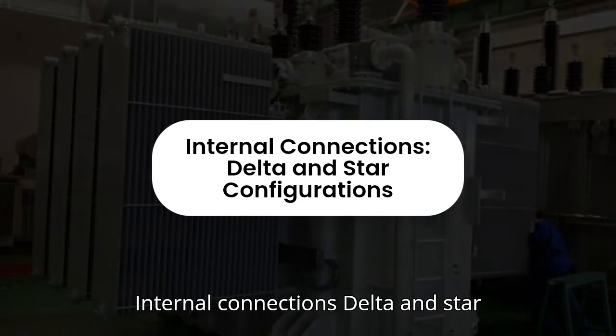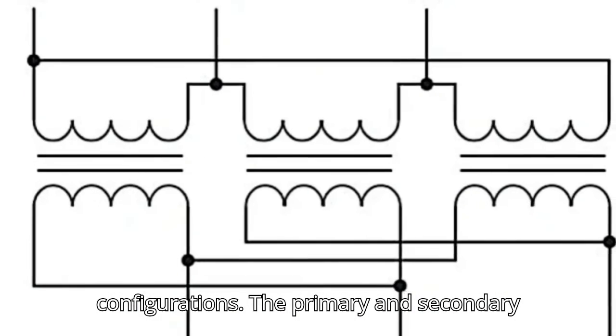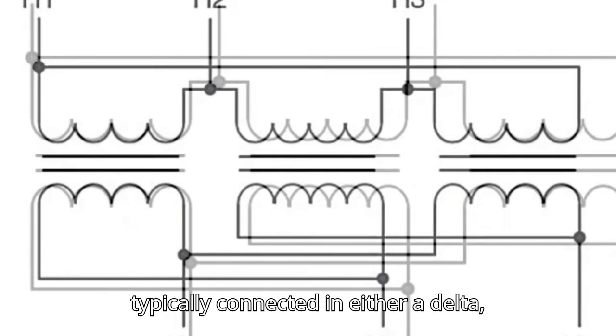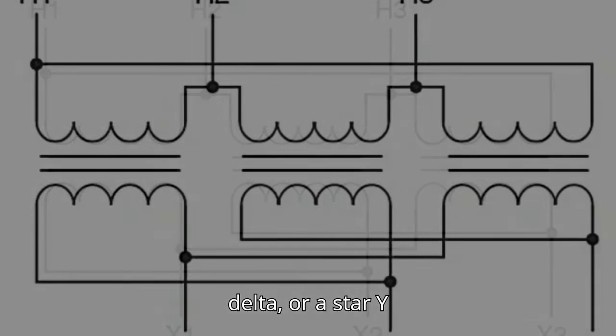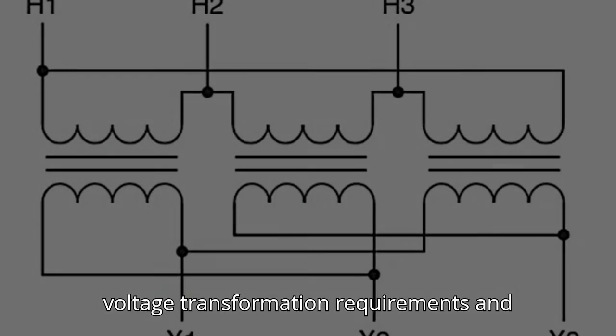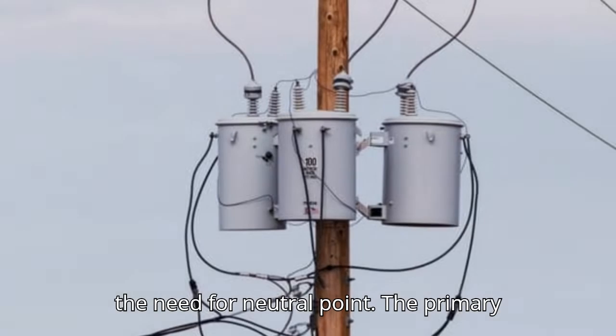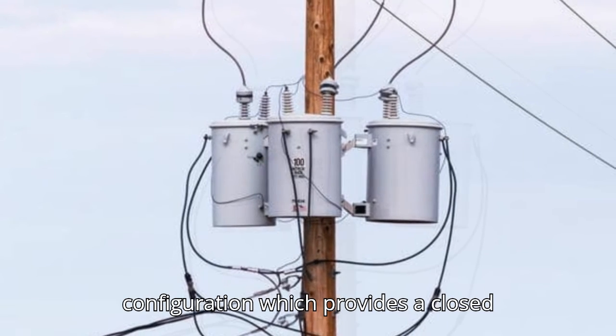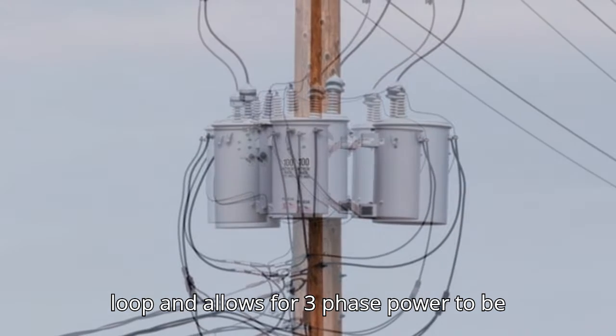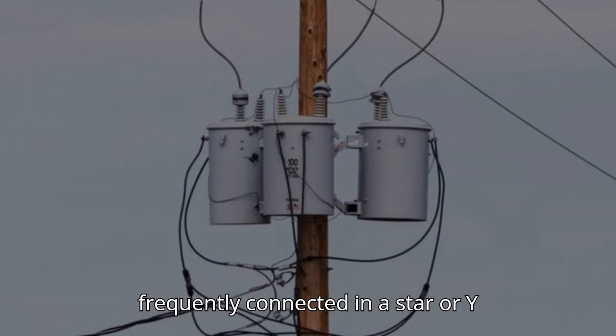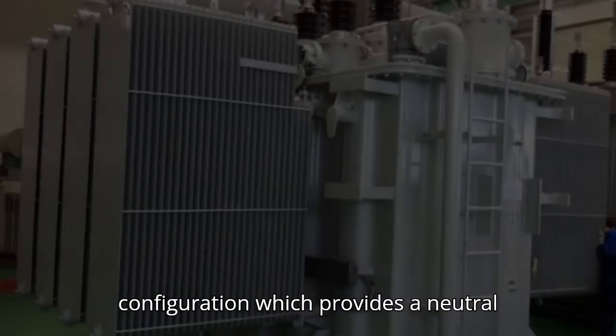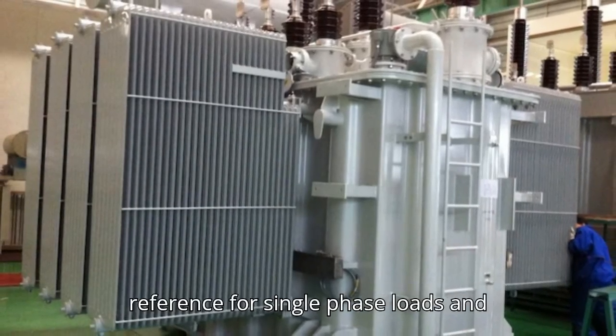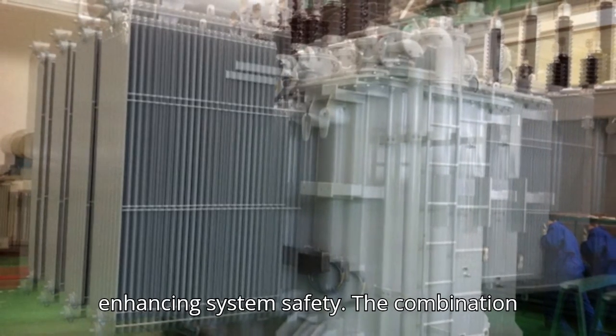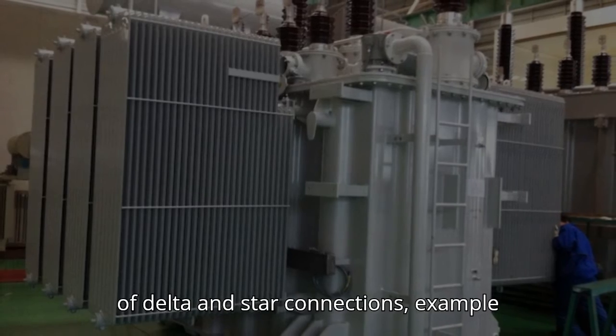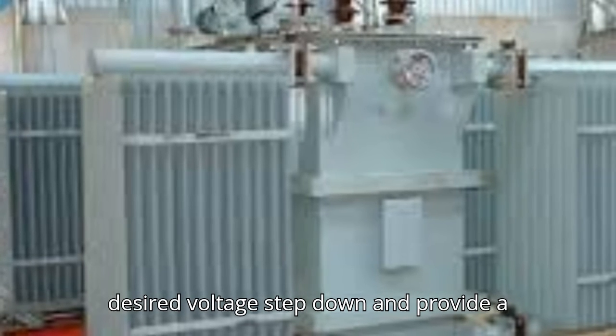Internal connections, delta and star configurations. The primary and secondary windings of distribution transformers are typically connected in either a delta or a star (Y) configuration, depending on the specific voltage transformation requirements and the need for a neutral point. The primary winding is often connected in a delta configuration, which provides a closed loop and allows for three-phase power to be applied. The secondary winding is frequently connected in a star or Y configuration, which provides a neutral point that can be grounded, offering a reference for single-phase loads and enhancing system safety. The combination of delta and star connections, for example delta-star or delta-Y, is common in distribution transformers to achieve the desired voltage step-down and provide a stable neutral.